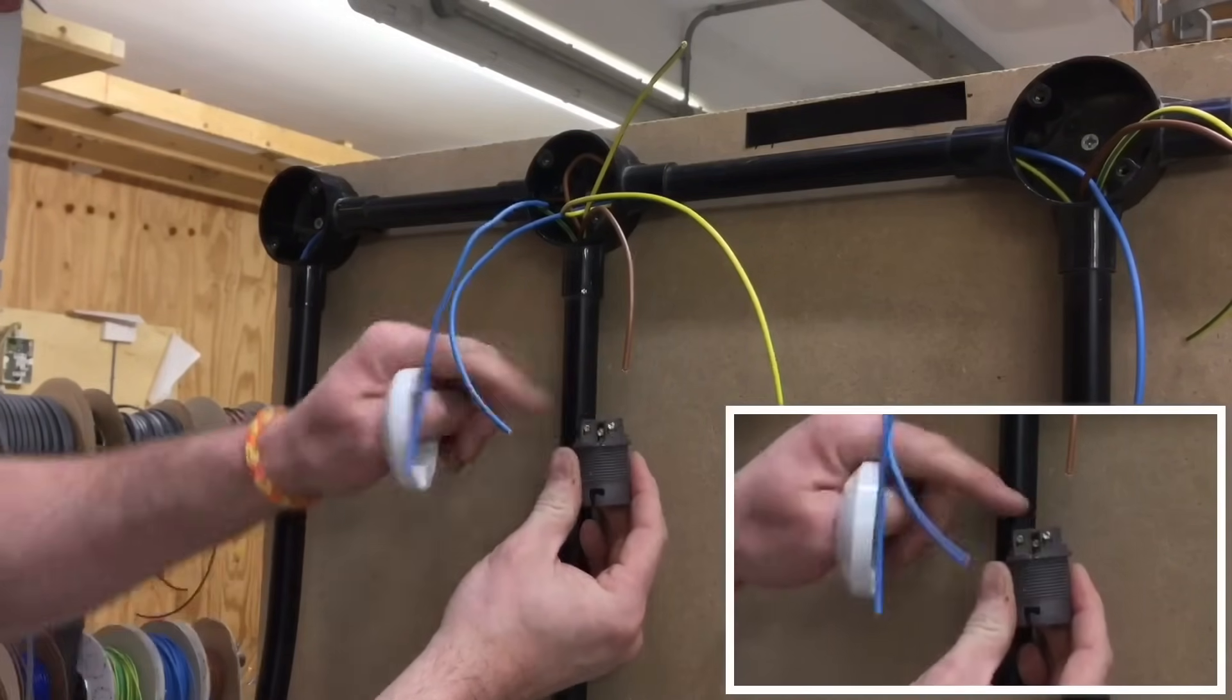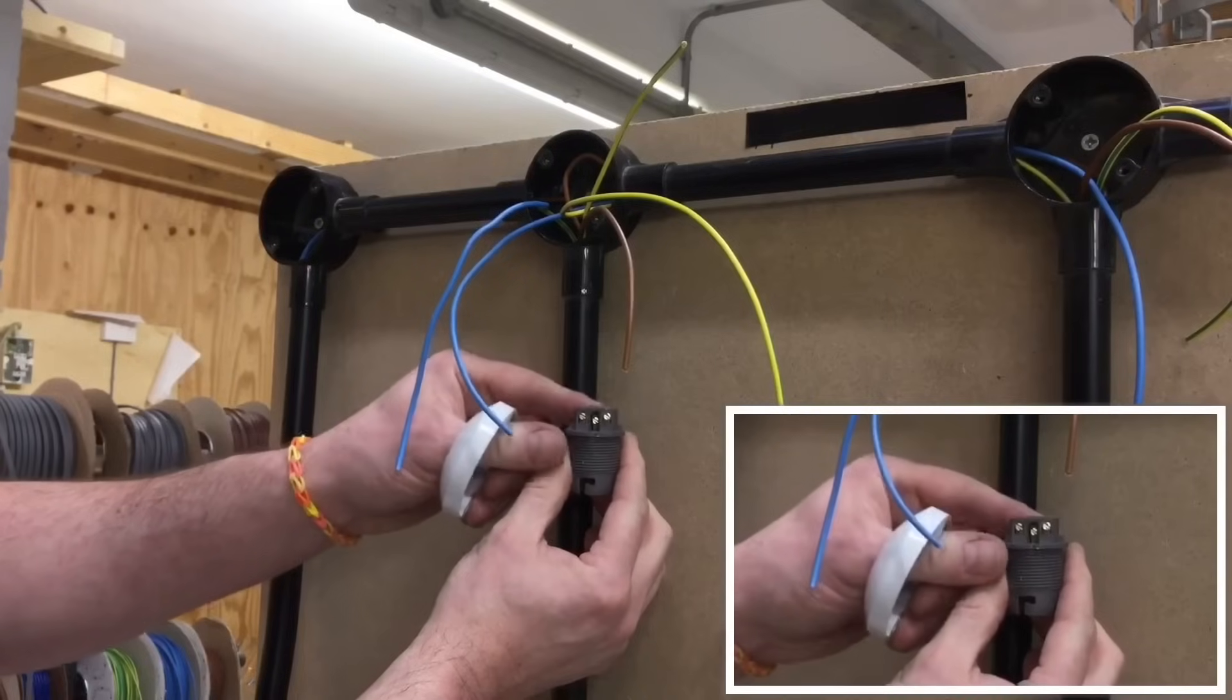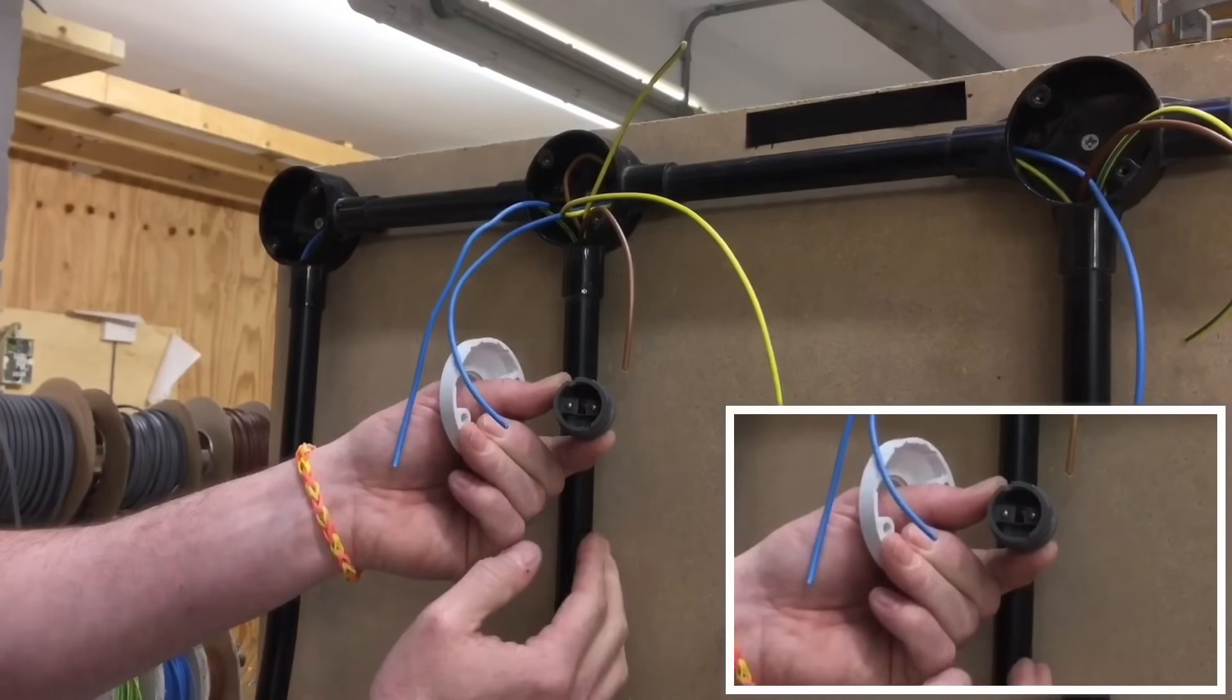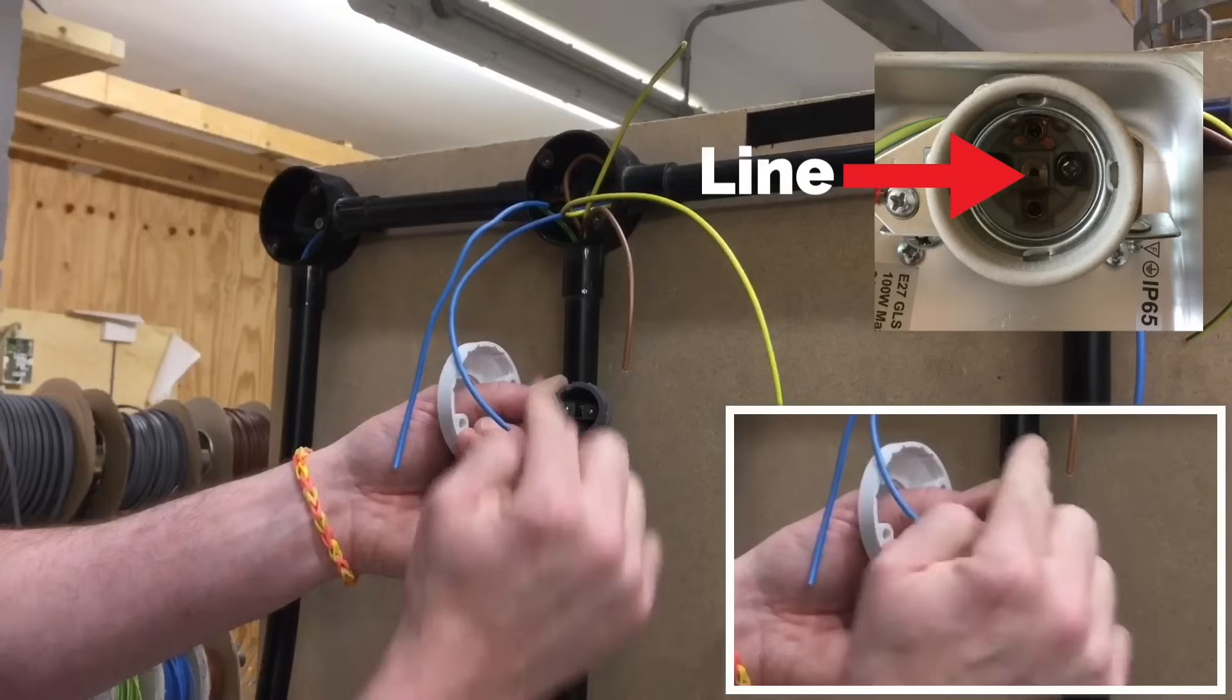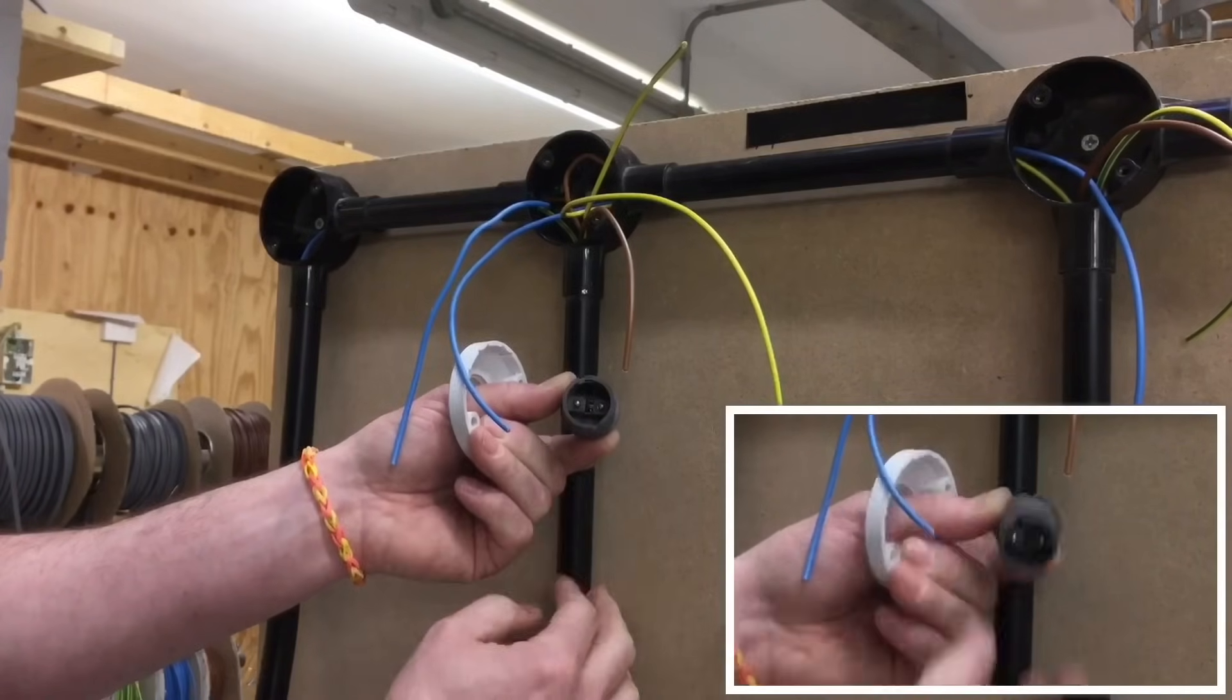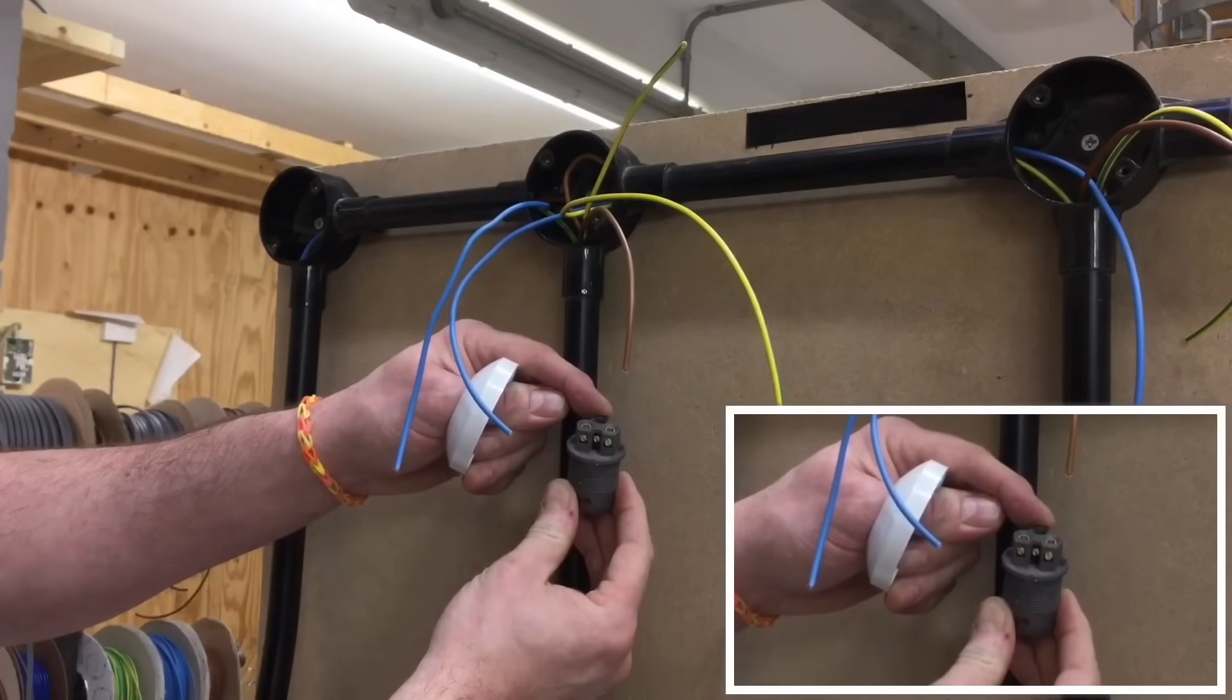This one here will be switching line or neutral. The reason being it's a bayonet cap lamp holder - the pins have no polarity, so it won't matter if I choose that one as the neutral and that one as the switching line or vice versa. The back section here is the connection for the circuit protective conductor. Be careful if you're using Edison screw style lamp holders that you actually polarize them - there'll be only one pin in the center which will be the line, and the screwed part will be the neutral. But we've got a bayonet cap one, so it doesn't matter which one's a switching line and which one's neutral.